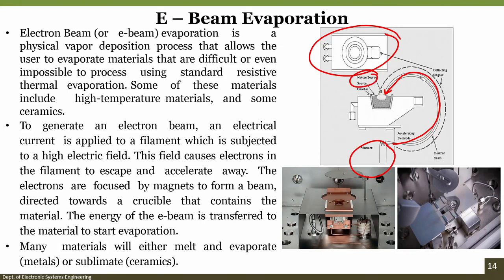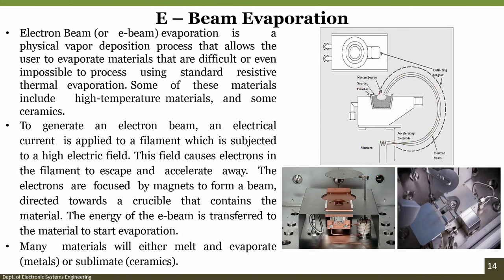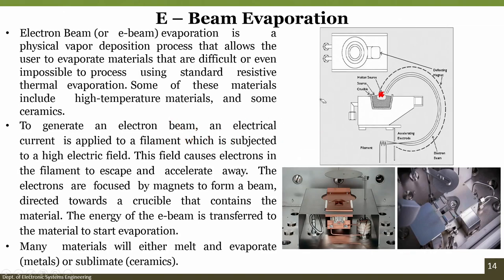You can change the amount of deflection and choose different evaporation modes: point evaporation, where the beam focuses on one spot; raster scanning, where it sweeps back and forth; or triangular wave scanning. Each has its own advantages and disadvantages. The key point is that the electron beam overcomes the limitation of thermal evaporation by directly melting the source loaded in the crucible.